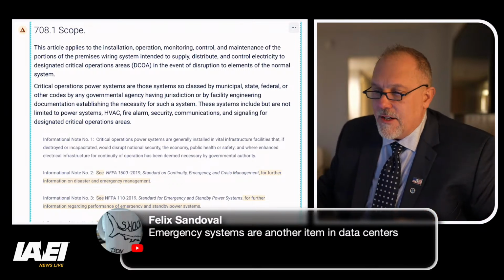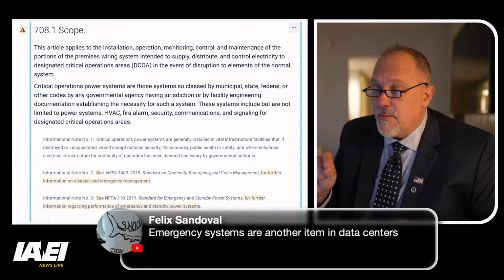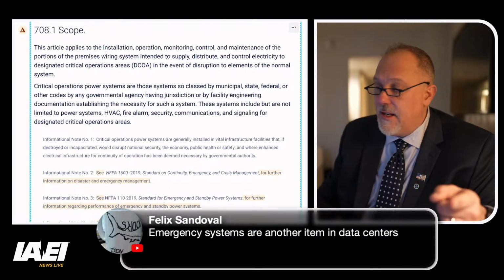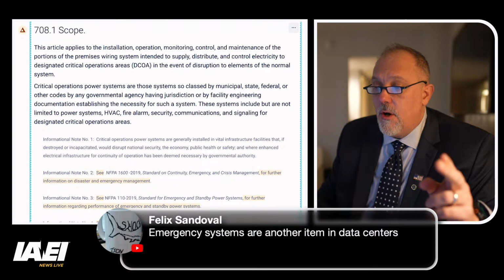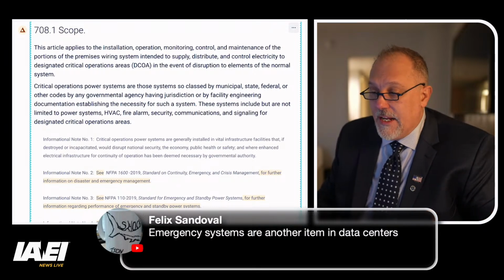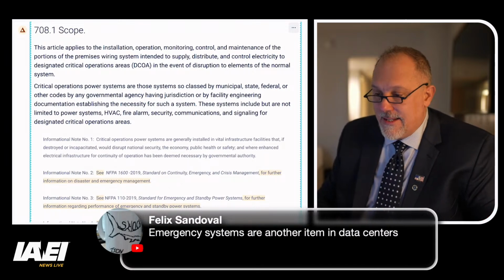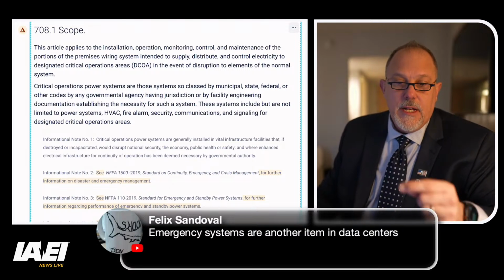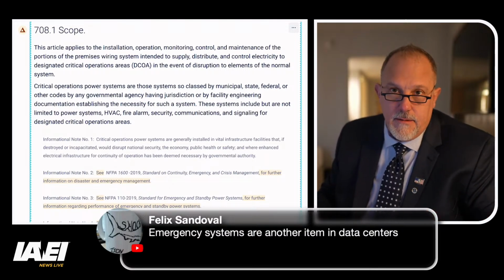It's meant to distribute and control electricity to designated critical operation areas in the event of disruption to elements of the normal system. Critical operation power systems are those systems classified by municipal, state, federal, or other codes by any governmental agency having jurisdiction. These systems include, but are not limited to, HVAC, fire alarm, security, communications, and signaling for designated critical operation areas. So somebody could say that a data center...